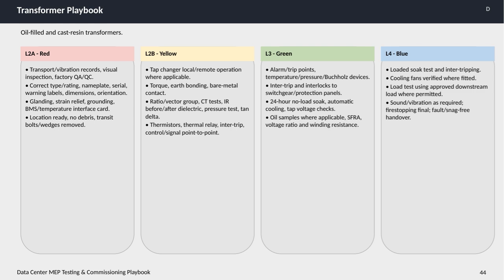We carefully review transport and vibration records and perform a thorough visual inspection alongside factory QA and QC. We verify the correct type and rating, check nameplates, serial numbers, warning labels, and ensure all dimensions and orientations are accurate. Important details like glanding, strain relief, grounding, and the condition of BMS or temperature interface cards are checked as well. The location must be ready, free of debris, and any transit bolts or wedges must be removed.